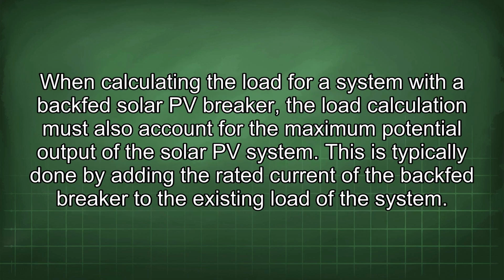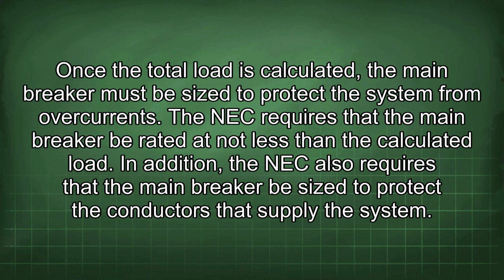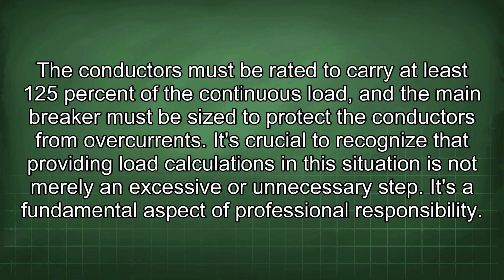When calculating the load for a system with a backfed solar PV breaker, the load calculation must also account for the maximum potential output of the solar PV system. This is typically done by adding the rated current of the backfed breaker to the existing load of the system. Once the total load is calculated, the main breaker must be sized to protect the system from overcurrents. The NEC requires that the main breaker be rated at not less than the calculated load. In addition, the NEC also requires that the main breaker be sized to protect the conductors that supply the system. The conductors must be rated to carry at least 125% of the continuous load, and the main breaker must be sized to protect the conductors from overcurrents.